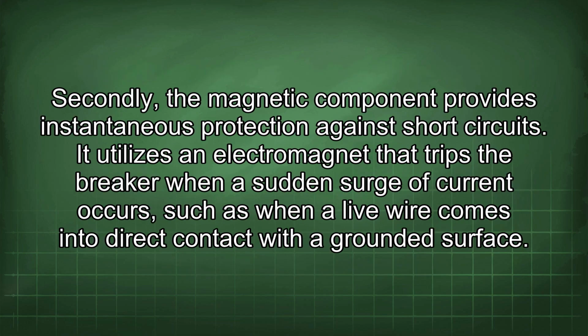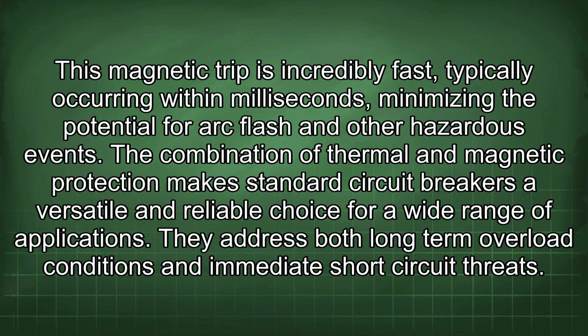Secondly, the magnetic component provides instantaneous protection against short circuits. It utilizes an electromagnet that trips the breaker when a sudden surge of current occurs, such as when a live wire comes into direct contact with a grounded surface. This magnetic trip is incredibly fast, typically occurring within milliseconds, minimizing the potential for arc flash and other hazardous events. The combination of thermal and magnetic protection makes standard circuit breakers a versatile and reliable choice for a wide range of applications. They address both long-term overload conditions and immediate short-circuit threats.